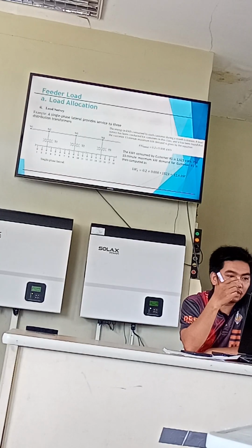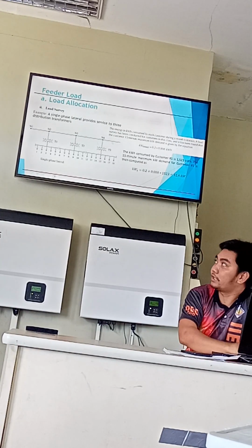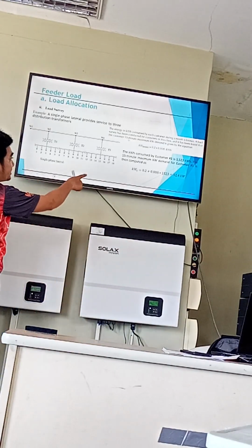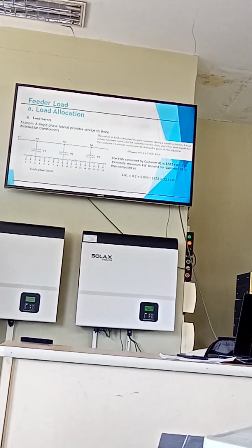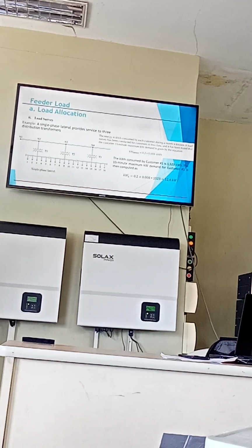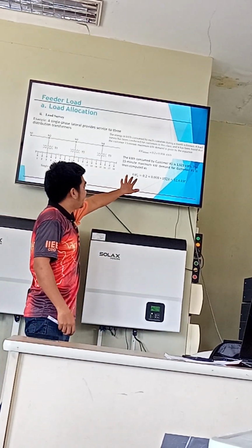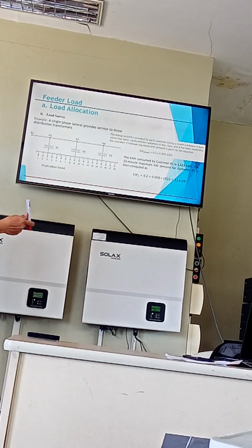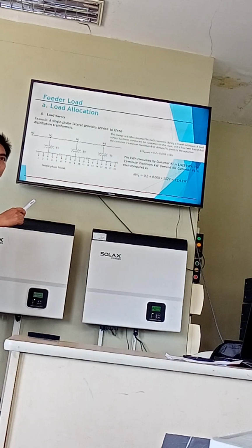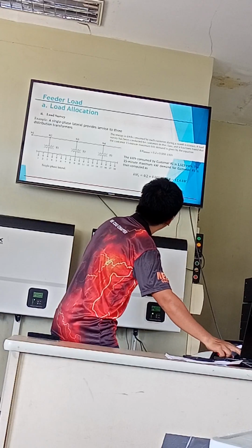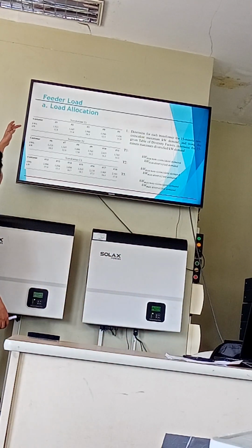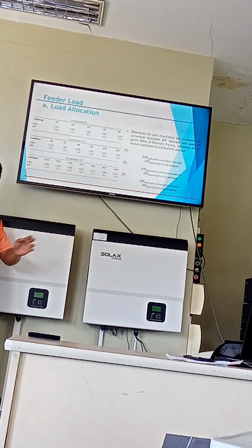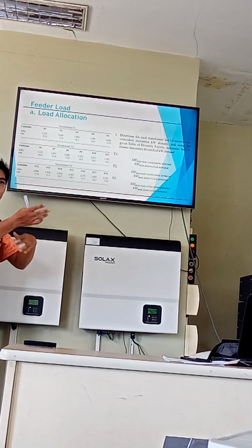For example, customer 1 has an energy consumption of 1,523 kWh on the bill. Using the equation, we can estimate the maximum kilowatts, which is 0.2 plus 0.008 times 1523, giving 12.4 kilowatts. Get it? The watts are important, later you will see the relevance. So for each kilowatt hour, there is an equivalent in kilowatts. That is how we derive the equation.